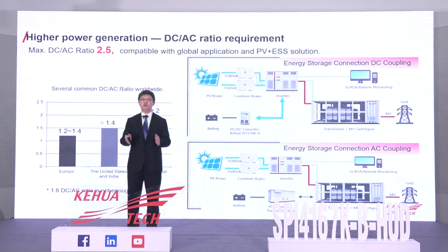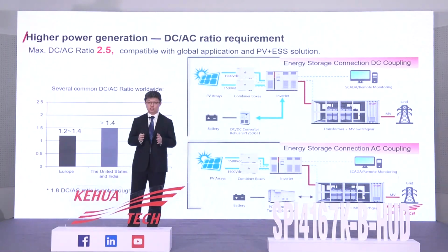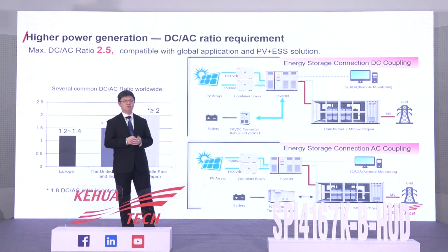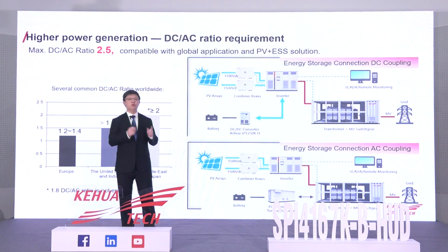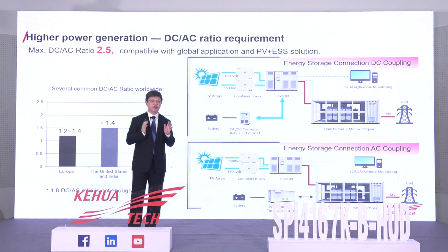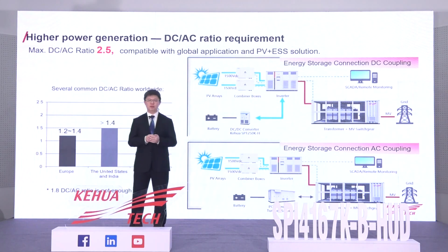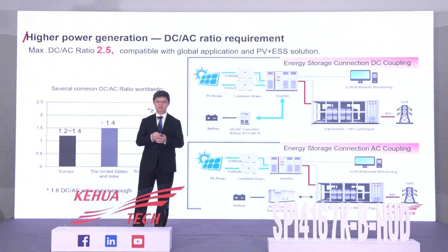The inverter needs to reserve DC capacity to connect to the ESS system. Based on our research, a 2.5 DC-AC ratio will meet the requirement of future PV plants and future PV plus ESS solutions.